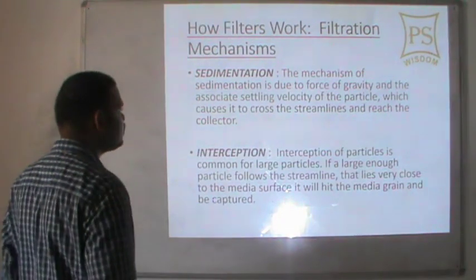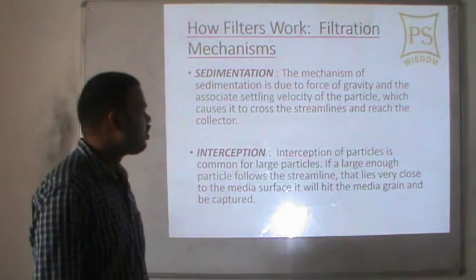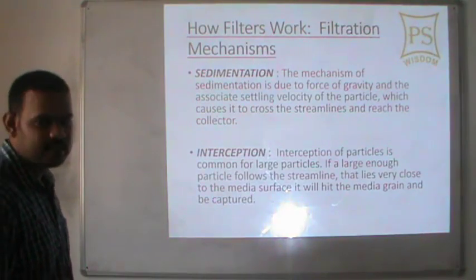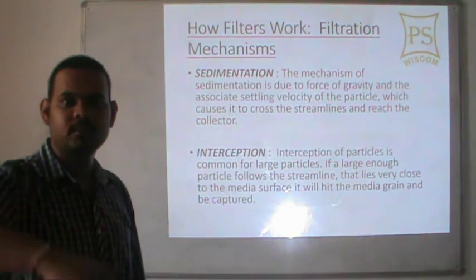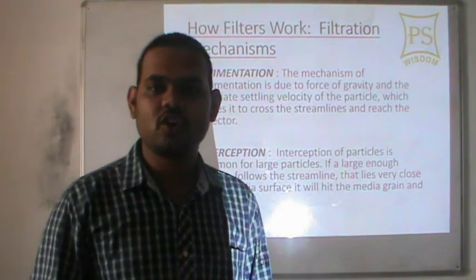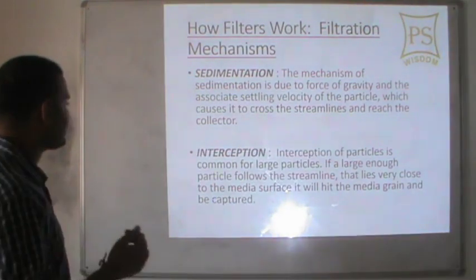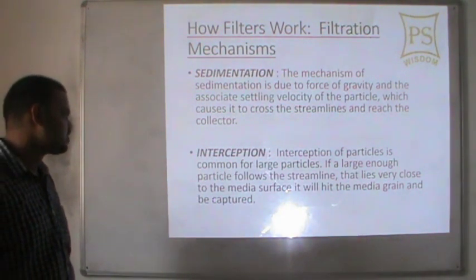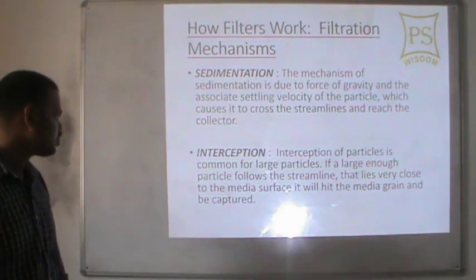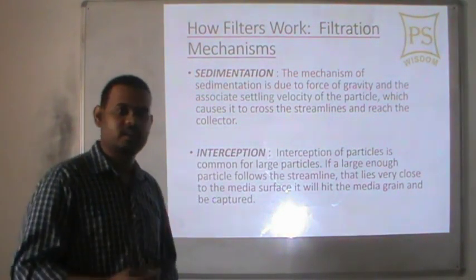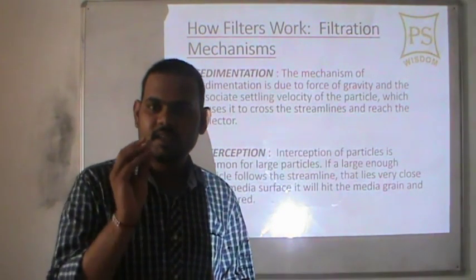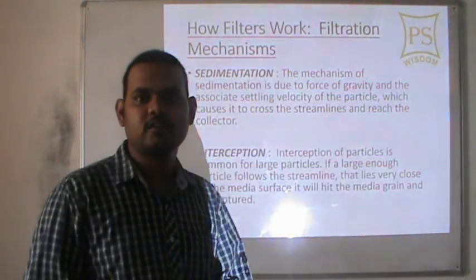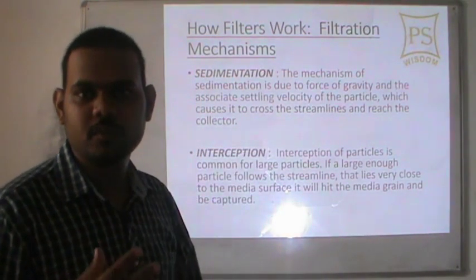In the sedimentation mechanism, due to the force of gravity and the associated settling velocity of the particle, the particle crosses the streamlines and reaches the collector. This is the first stage of filtration in the filtration chambers. The second mechanism, interception, is common for large particles: if a large enough particle follows streamlines that lie very close to the media surface, it will hit the media grain and be captured.